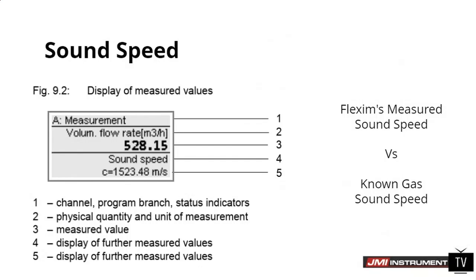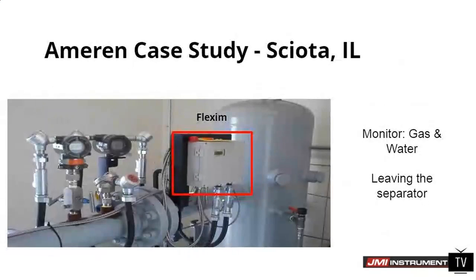This is just one of the first meters that I did here at Flexim about 10 years ago. This is at an underground gas storage site. Basically, we have a meter here that's measuring standard volume flow. We have a pressure and a temperature transmitter that go into the meter, and we're correcting for standard volume. This is the older platform meter, the 704, not the 721, but essentially they do the same thing.